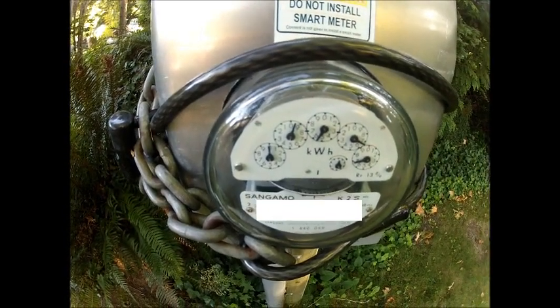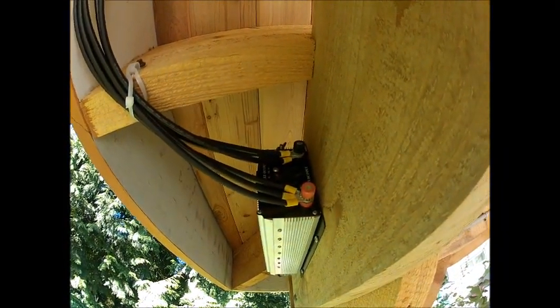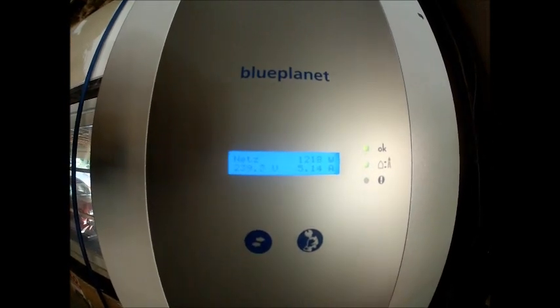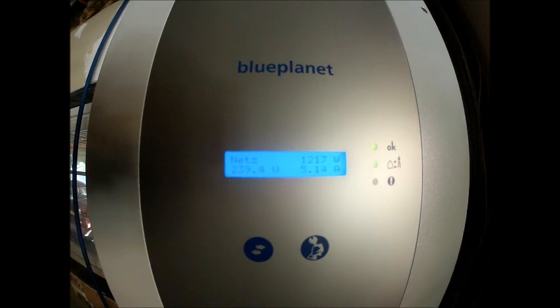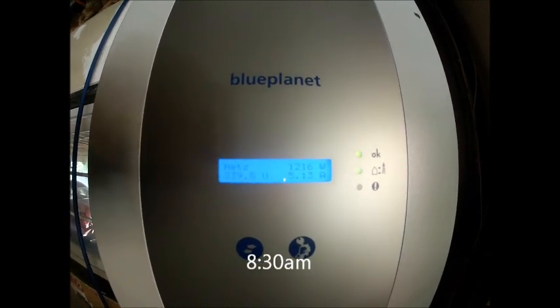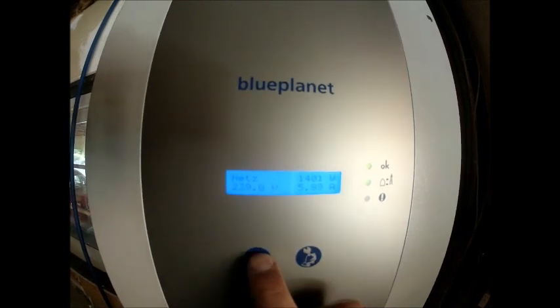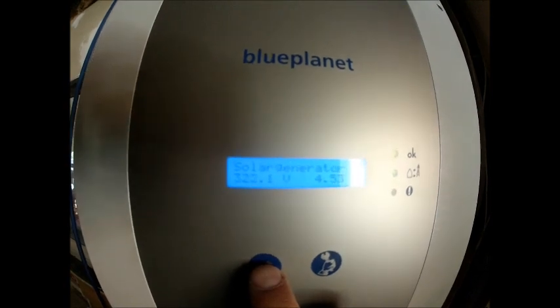We'll see what happens later in full sun on how fast the sucker goes. We've got some decent sun on these three and the inverter is running fairly well — we're not at peak output but that adds to the total as well. Now it's about 8:30 and we've got 1.2 kilowatts. Sun is on the panels but at quite an angle so we're nowhere near midday. We're at 1.4 kilowatts now — 240 volts house power, 5.9 amps going in. On the DC side, the solar is at 335 volts and 4.5 amps.